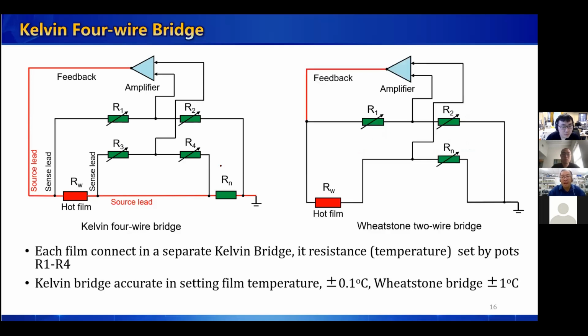If you compare the 4-wire Kelvin bridge with the Wheatstone bridge, their difference is dramatic. The Wheatstone bridge only has 2 wires. Both the sensing lead and the source lead are the same set of wire. The bridge will also go to balance, but the Kelvin bridge will set the film temperature at a much more accurate temperature than the Wheatstone bridge. And this 0.1 Celsius uncertainty in temperature makes a lot of difference. This is actually one of the core technologies of this method. If we use the regular Wheatstone bridge, this will not work. I will explain why later on.